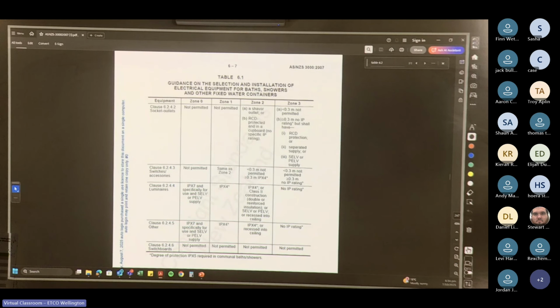So the majority of the light fitting is in the ceiling, but we can get IP rated downlights. And again, for anything else apart from switchboard, IPX4 or recessed into the ceiling. So that would be for things like, I have seen them installed, the sound system inside of the bathroom, so you can rock out to tunes while you're doing your business or having a shower.